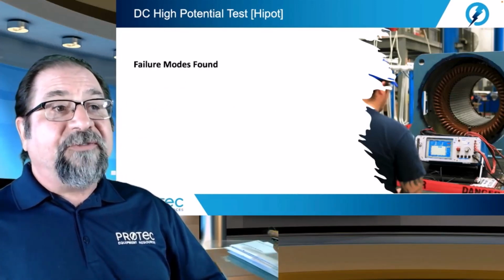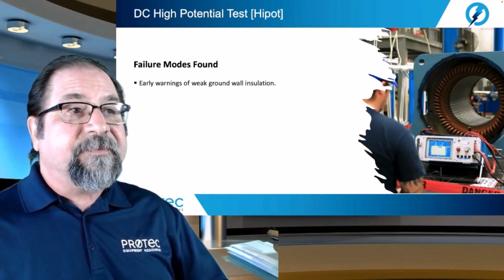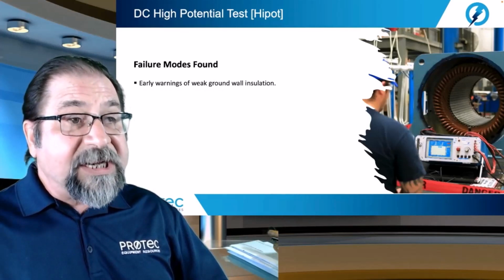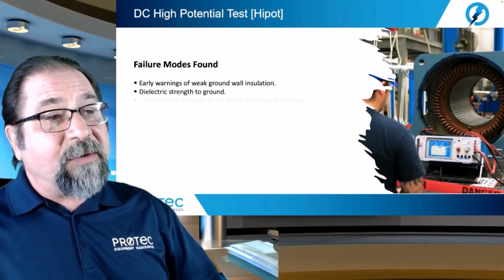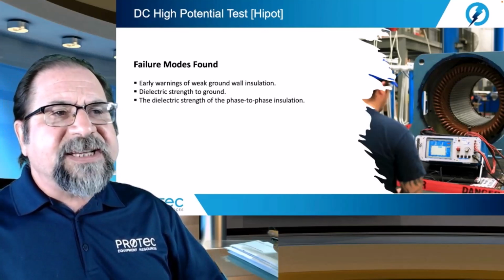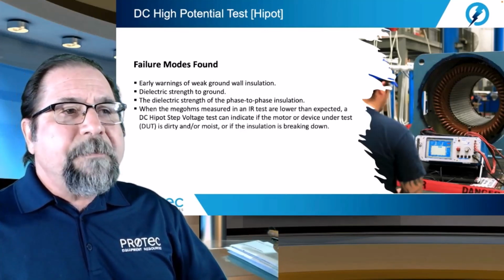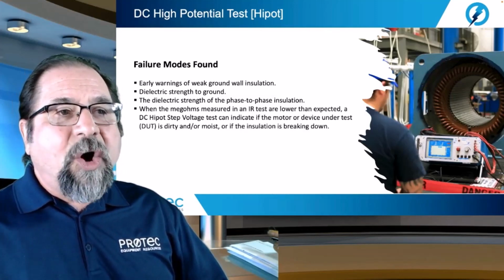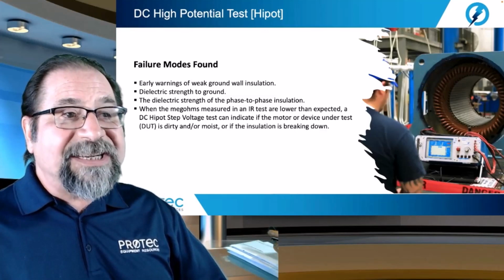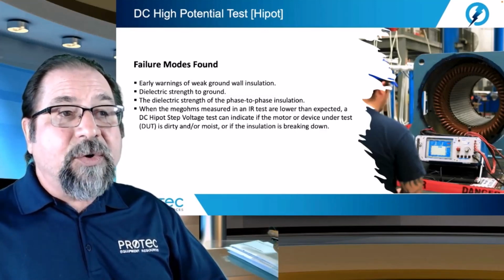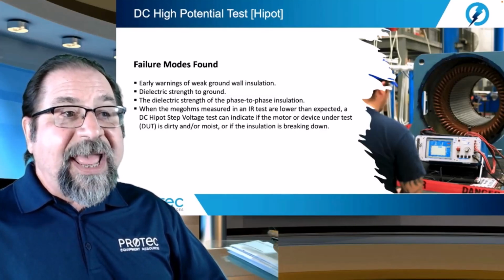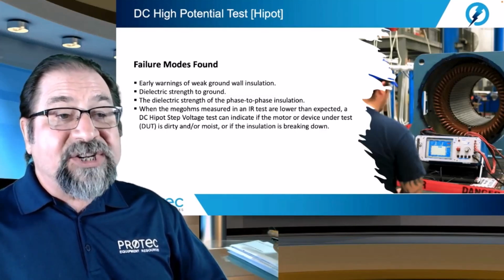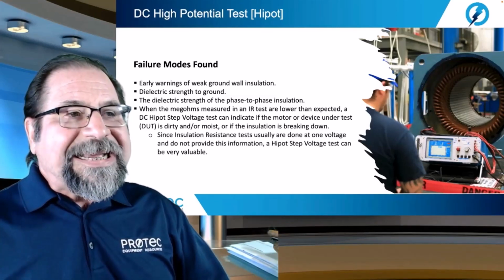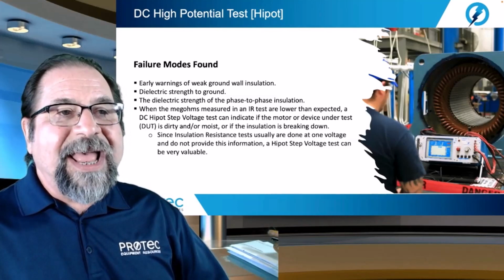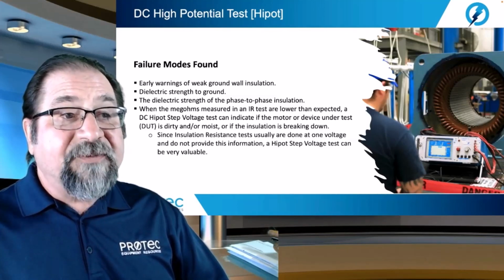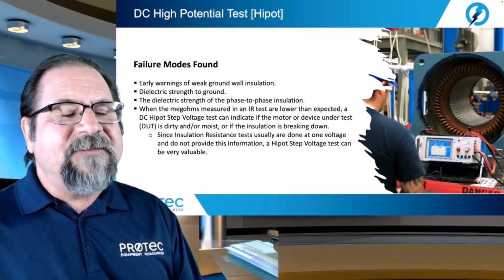And what are the failure modes that we can find with a high pot? Early warnings of weak ground wall insulation. Dielectric strength to ground. The dielectric strength of the phase-to-phase insulation. When the megohms measured in an insulation resistance test are lower than expected, a DC high pot step voltage test can indicate if the motor or device under test is dirty and or moist, or if insulation is breaking down. Since insulation resistance tests usually are done at one voltage and do not provide this information, a step voltage test can be very valuable.